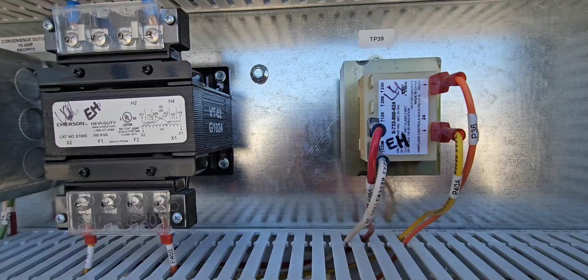Okay, pro tip for today. Transformers are very important, to check to make sure that they're tapped correctly, especially on racks when you're using transformers to step down your control voltage, stuff like that. You need to make sure that you are tapped correctly. And what I mean is, if you look on this transformer right here, we've got our common, which stays the same, but then we have 120, 208, 240. Now, a lot of the times 208, 240 is used kind of interchangeably.